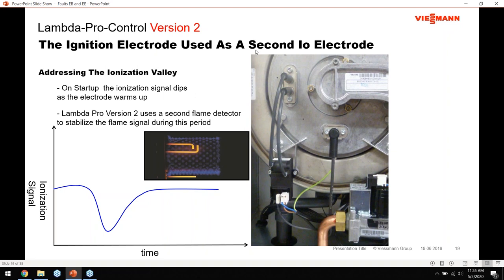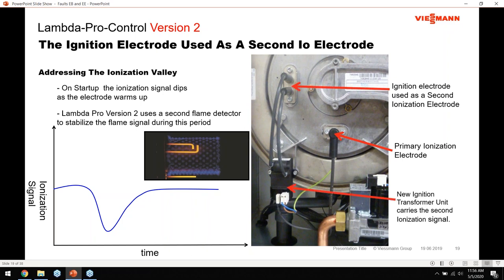Getting back to the Lambda Pro system: you can see the burner firing with the flame rod and ignition electrodes visible. The flame rod is the primary ionization signal, with the burner ground plugged in behind it. The ignition electrode is positioned at about the nine o'clock position on our boilers. This is a different ignition transformer and ignition electrode system than was on the previous generation WB-2B - we changed to a Lambda Pro version two system. The primary difference is the ignition transformer and electrode, with a second reference point that Lambda Pro now uses.